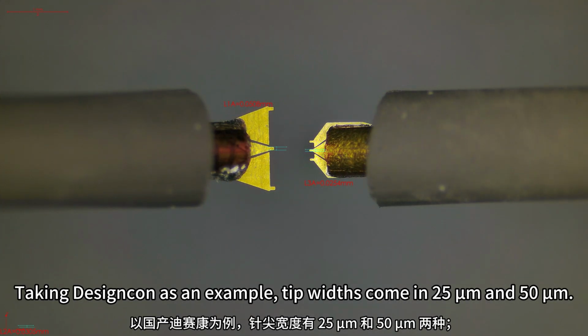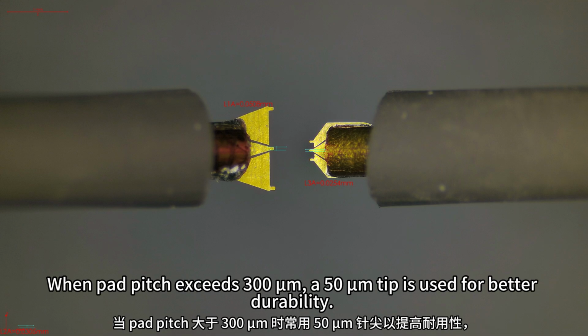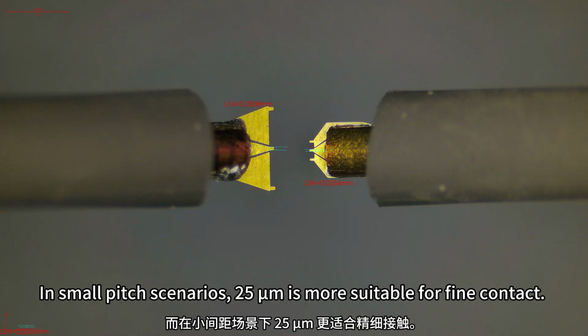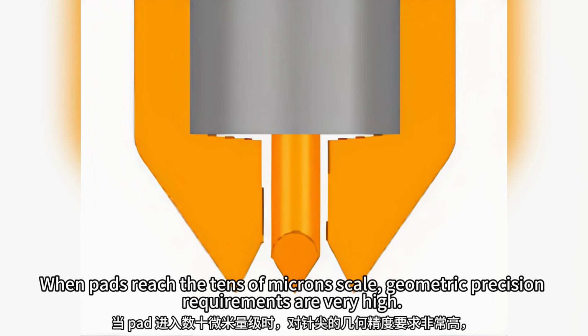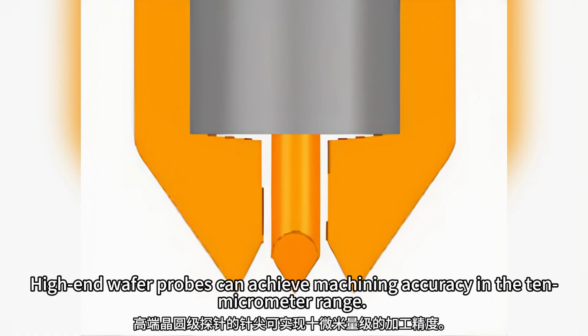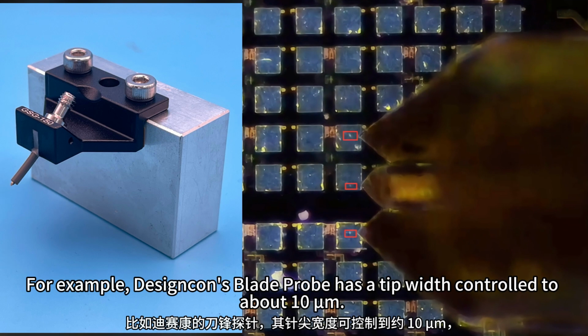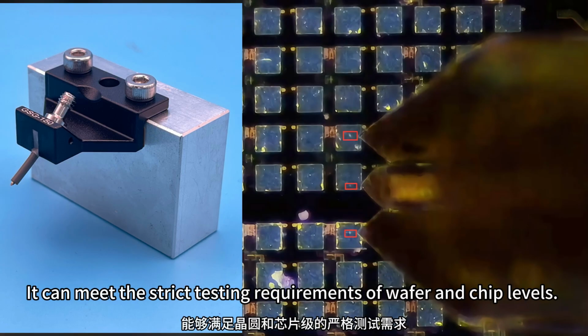Taking Designcon as an example, tip widths come in 25 micrometers and 50 micrometers. When pad pitch exceeds 300 micrometers, a 50 micrometer tip is used for better durability. In small pitch scenarios, 25 micrometers is more suitable for fine contacts. When pads reach the tens of micron scale, geometric precision requirements are very high. High-end wafer probes can achieve machining accuracy in the 10 micrometer range. For example, Designcon's blade probe has a tip width controlled to about 10 micrometers. It can meet the strict testing requirements of wafer and chip levels.